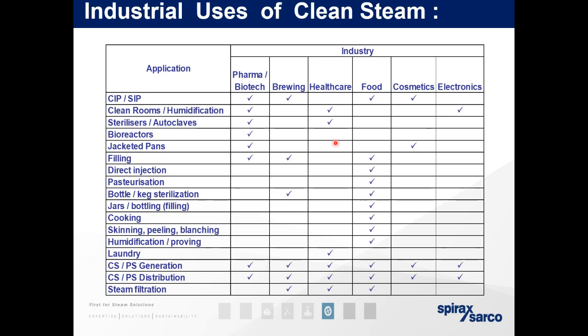Laundry will be used in healthcare. They need to clean the scrubs. CS and PS generation, all industries. And distribution, all industries again. Steam filtration, mostly found in brewing, healthcare and food. The reason why we're not showing pharmaceutical on steam filtration is because they tend to be clean steam loops. So again, as we were speaking, demineralized water, where the water is actually different to your standard boiler. It's a closed system and there tends to be very little, if any, return of condensate.